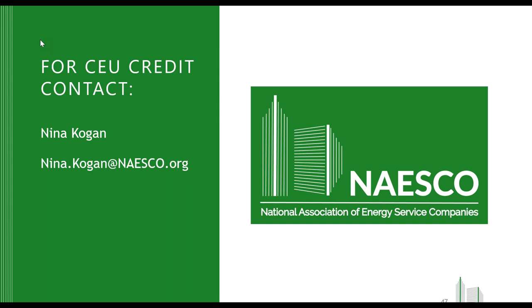And also not a lot of testing being required in different areas of the country for codes and things like that. So there's not really a rule of thumb based on age. For us, the rule of thumb for good candidates for energy savings is large buildings. Buildings that I can't throw a baseball over is what I call large. So those are always good candidates for us. Anything that's running a lot of high static pressure, anything that has high outside air or high occupancy are great candidates for us. And yeah, that pretty much is what we look for the most.